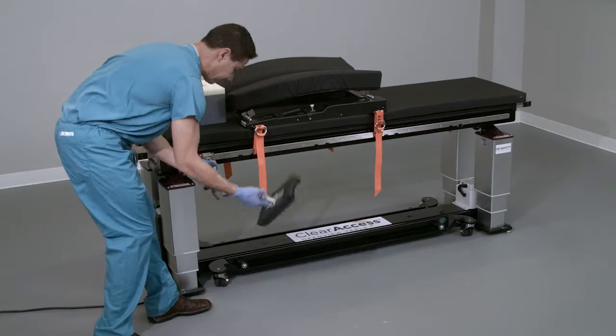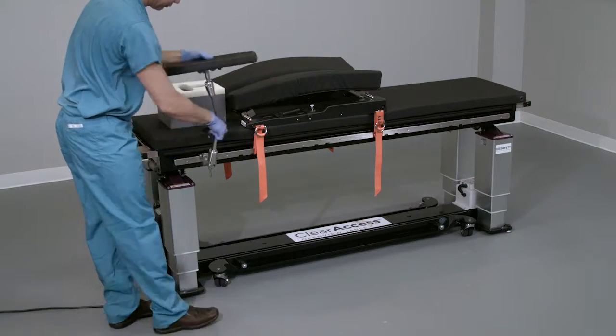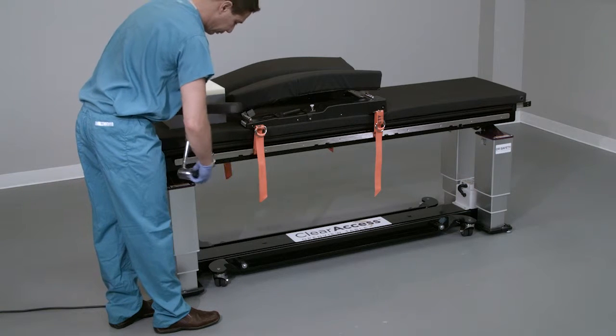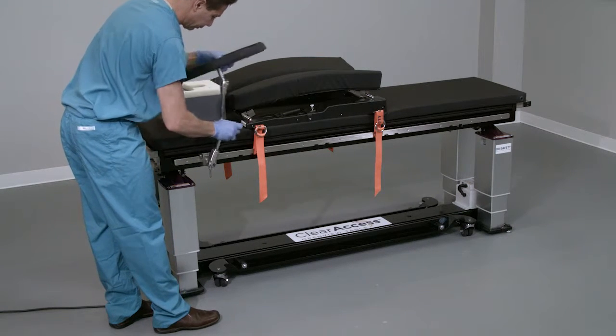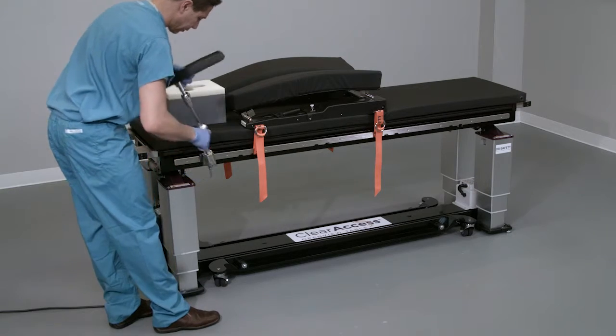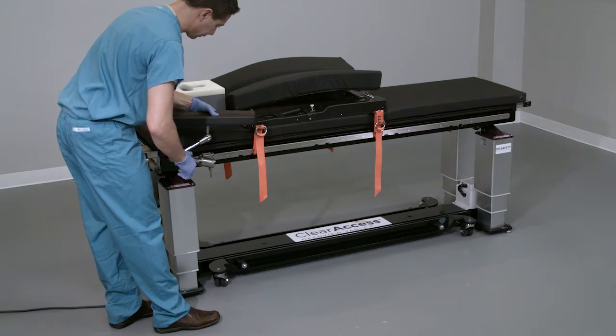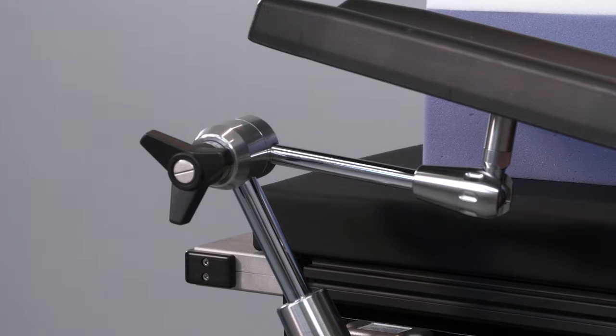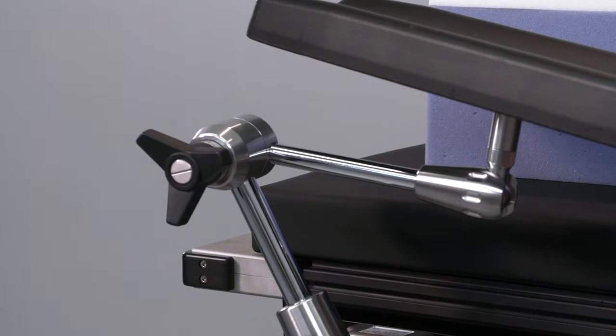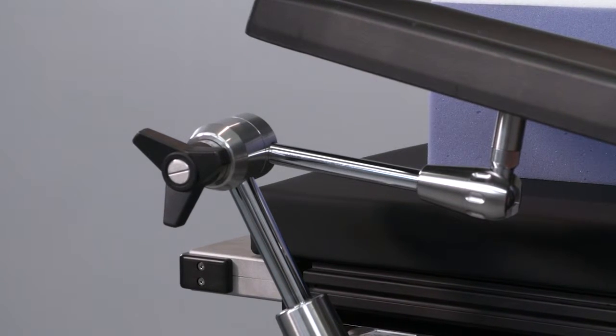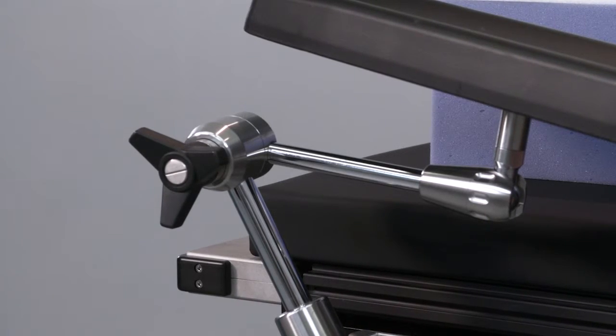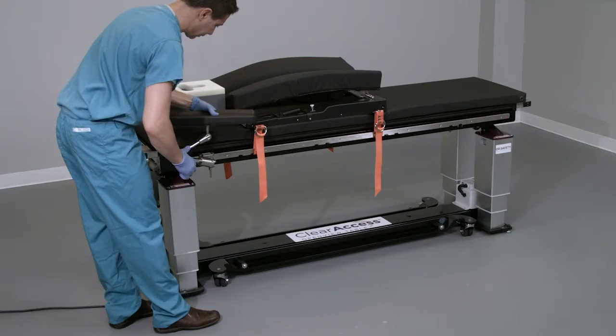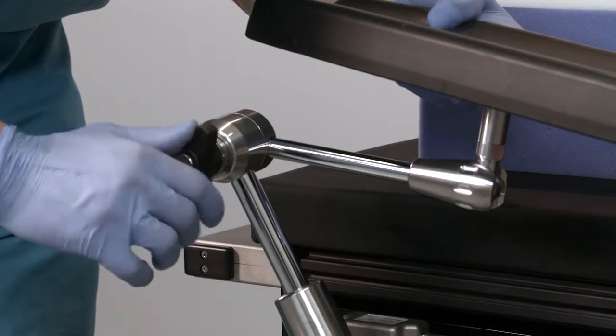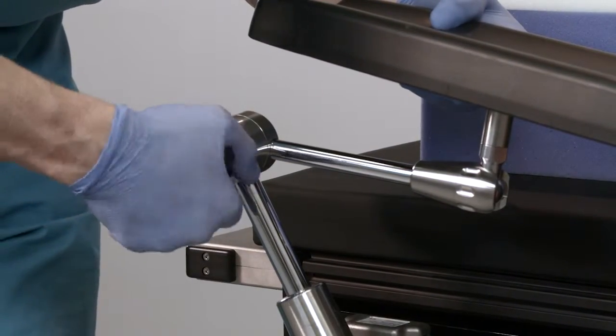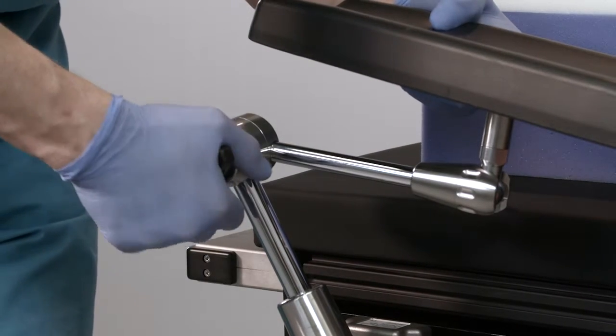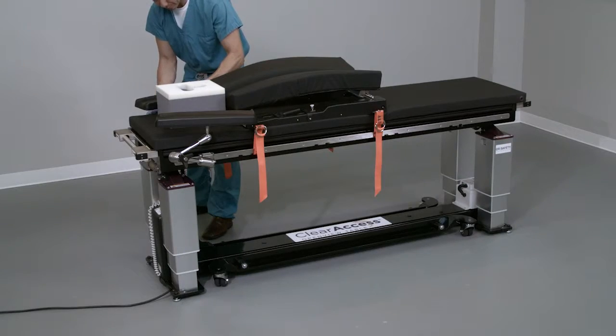Once the armboard has been attached to the side rail, it's possible to arrange the armboard in an unlimited number of positions by supporting the armboard with one hand while moving the elbow of the armboard to a desired location. It's advisable to place the armboard lock and the elbow of the armboard toward the head end of the table rather than the foot end to prevent interference with the surgeon during the procedure. Once satisfied with the location of the armboard, lock the armboard in place by hand-tightening the large black knob at the elbow.